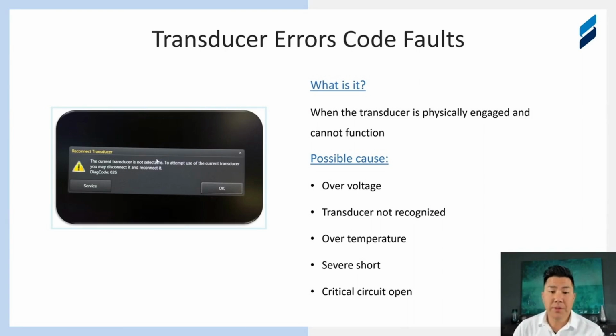Other times transducers just don't run, and you can see here that this is an example of a fault when you're trying to engage a transducer. The moment the machine tries to fire all those relays to get this probe running and start sending power, boom, you get this error message. Obviously, we're trying different ports. We've identified it's the probe, and this can mean several things. First and foremost, the probe just doesn't run. It's just not going to run, and the machine just spits up an error and says, hey, there is something massively wrong with this. This is not just an image quality issue. Like there's a circuit here that is really out of order, and I can't run this probe.